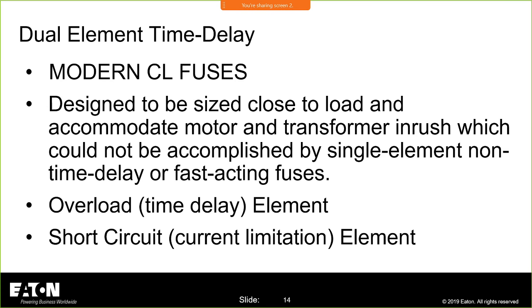fuses, current limiting in nature. They are basically designed, and I'll show you, it really gets back to the trip curve. I'm a TCC, time current characteristic kind of guy, and that's really where you'll see the benefit of a dual element time delay fuse. Again, you'll see these on motors and transformers because they provide very good short circuit protection, but yet they let the equipment start. If it's a transformer, they'll let it energize. If it's a motor, they're going to let it start. So you have an overload time delay element and a short circuit element.